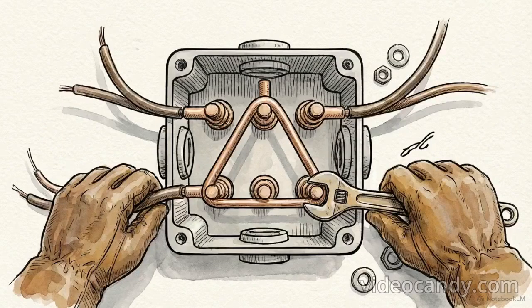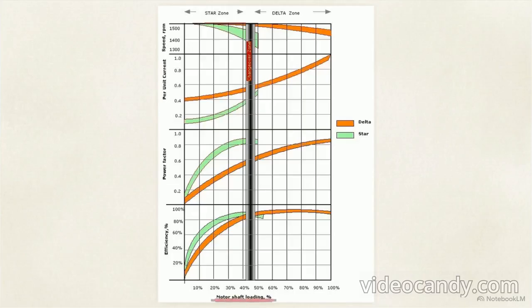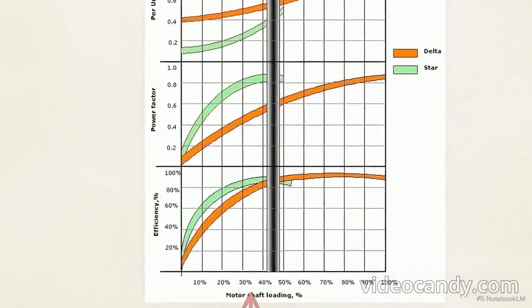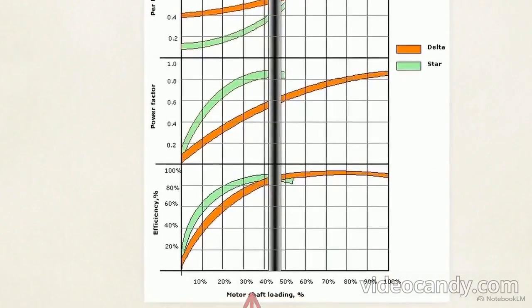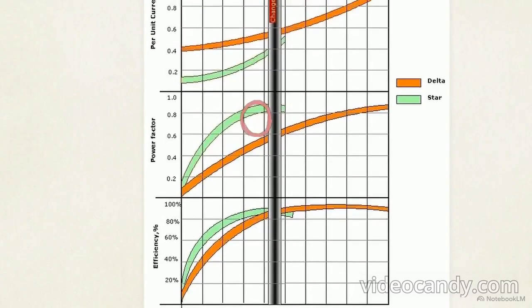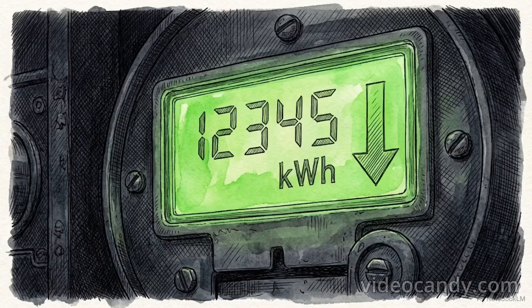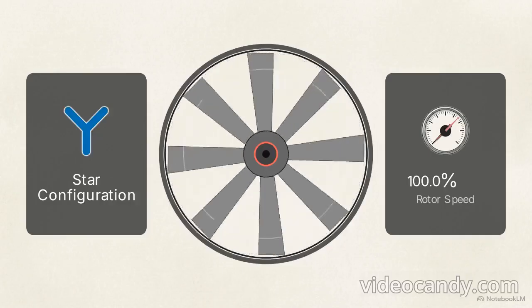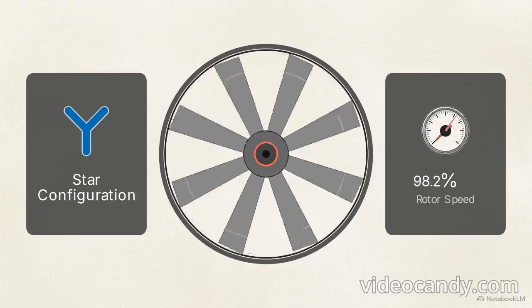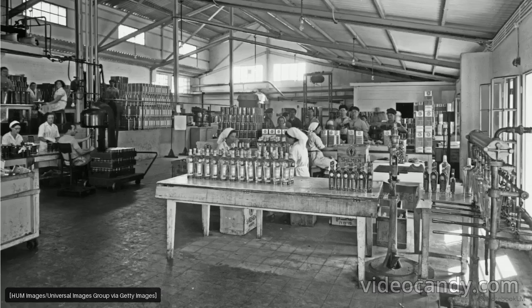If a delta-connected motor is continuously running below 30% of its rated shaft load, it operates with severe inefficiency. It draws excessive magnetizing current from the grid just to maintain a magnetic field it isn't fully using. Engineers can implement a targeted efficiency hack, intentionally taking an underloaded motor and rewiring it to run permanently in the star connection. By plotting efficiency and power factor against motor shaft loading, the green star curve outperforms the orange delta curve below the 30% threshold. Applying the lower star voltage reduces magnetic field strength, slashing iron core losses, and drastically improving power factor.